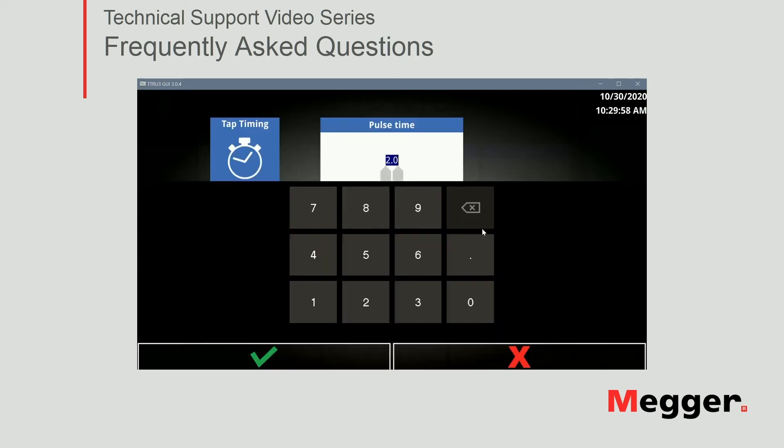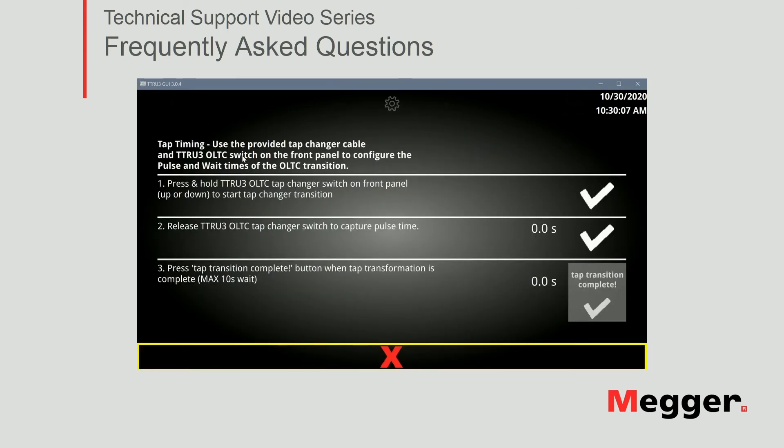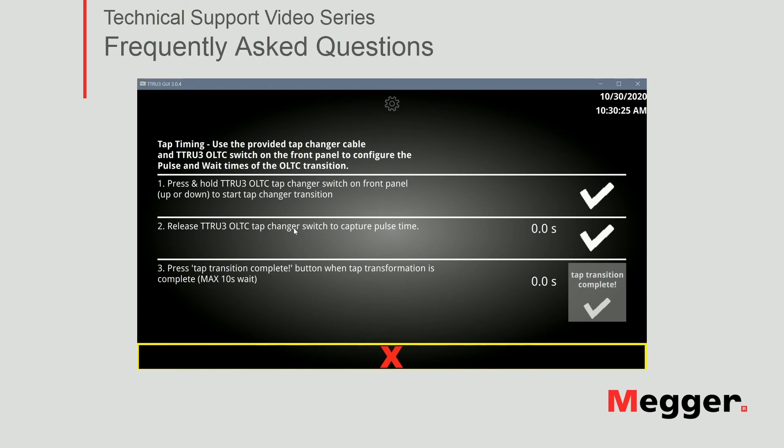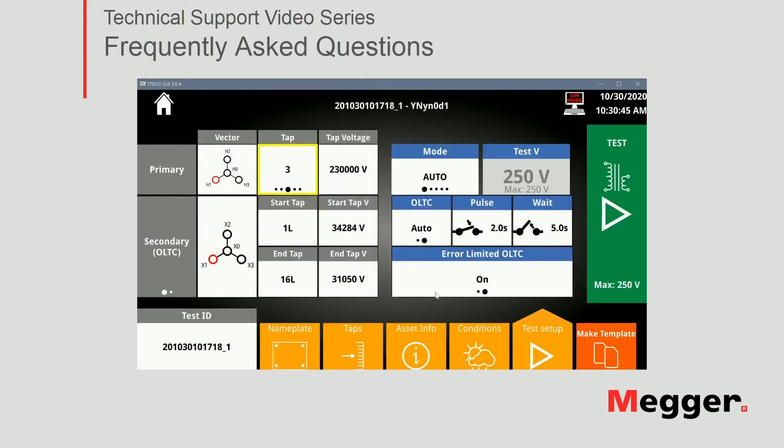Two ways to do so. First one is just manually inputting the times in seconds, if you know the tap changer. But if you do not, you can use the tap timing functionality. So you press this icon to get the instructions on screen. But basically what you have to do is just press either the up or down button for that switch in the OLTC on the instrument, on the top panel of the instrument. And when you release the switch, it will capture the pulse time, right? Then you press the tap transition complete button. So the software also learns the wait time for the OLTC to complete the transition. So a little bit of automation as well to learn the pulse and wait times.